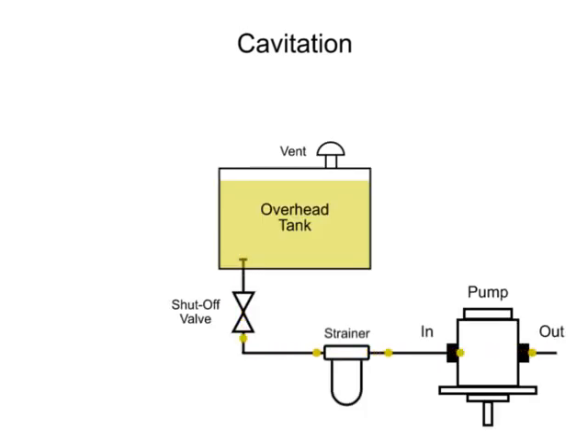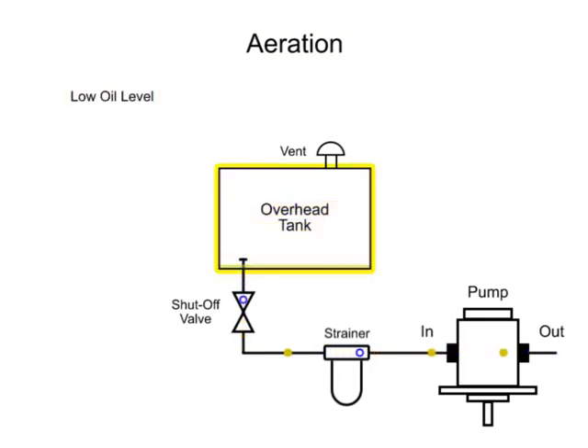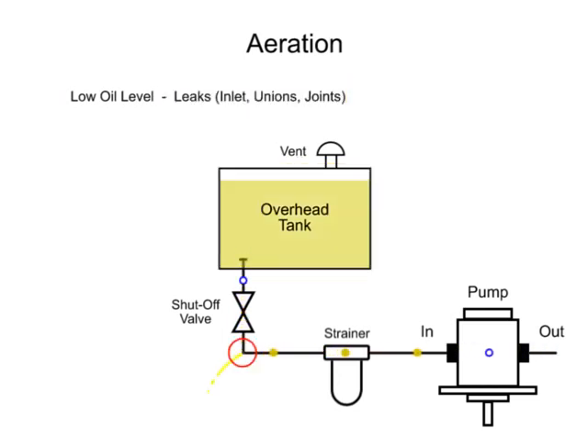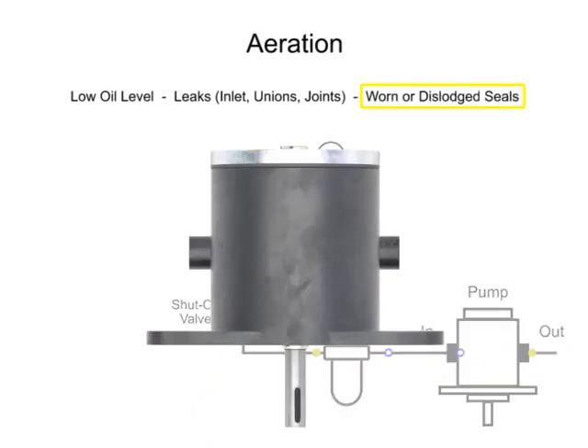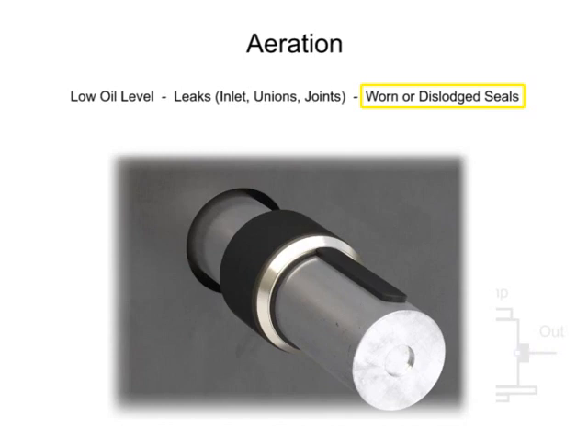Another form of cavitation is called aeration and is caused by air entering the oil stream. This can occur for a variety of reasons, including a low oil level in the reservoir, leaks in the inlet plumbing line — especially at unions and joints — and worn or dislodged seals in other hydraulic components such as pumps, cylinders, or valves.